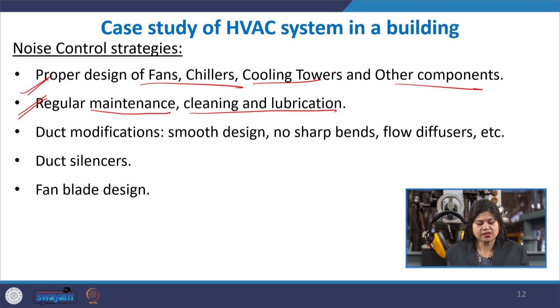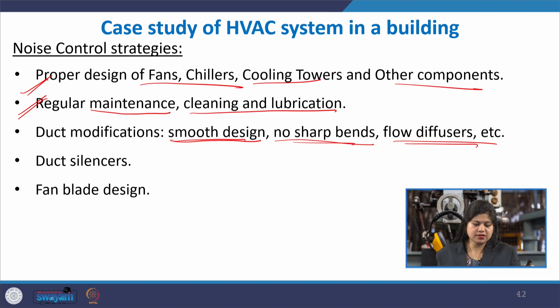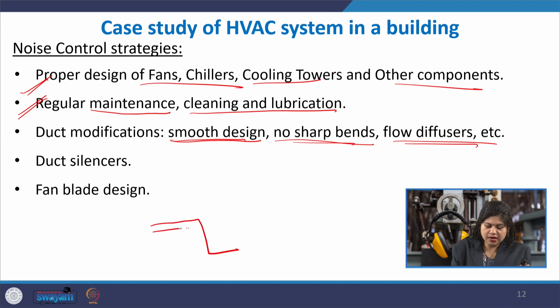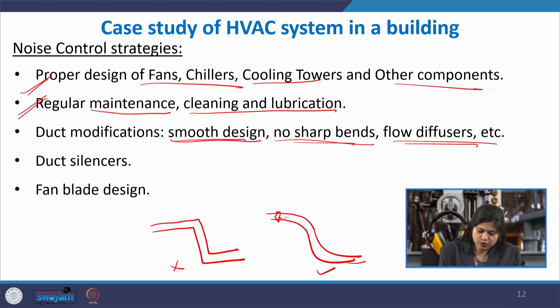Modifications to the duct itself can reduce duct noise: ducts can be designed with smoother profiles without sharp bends, or flow diffusers can be installed. As discussed in the previous module, the less resistance offered to air or fluid flow inside the duct, the less noise is produced. More streamlined duct designs create less turbulence, and installing flow diffusers makes the flow more laminar even if turbulence exists upstream.